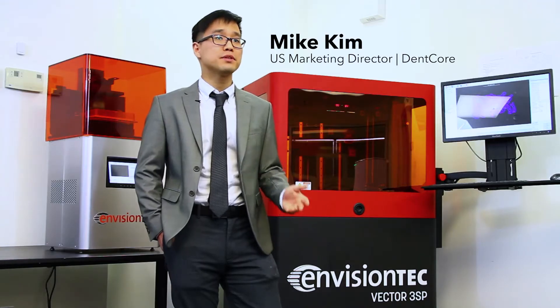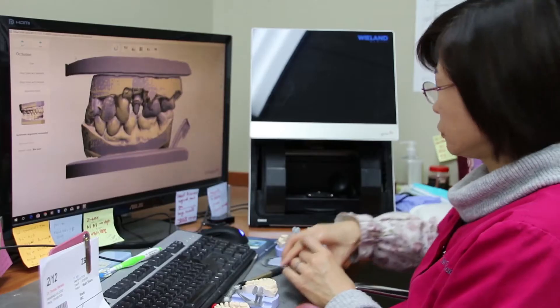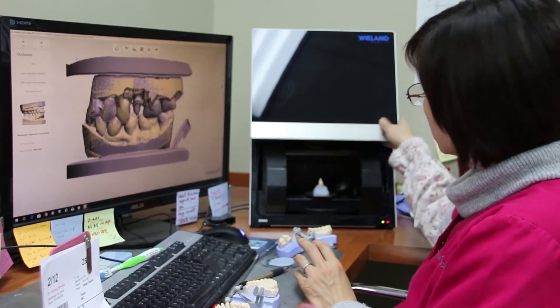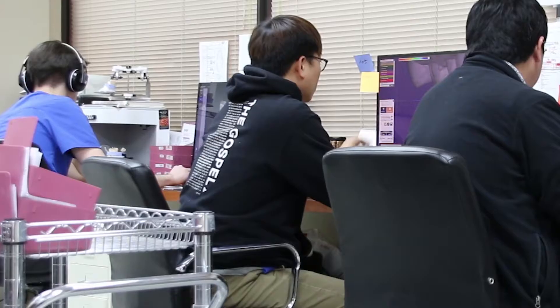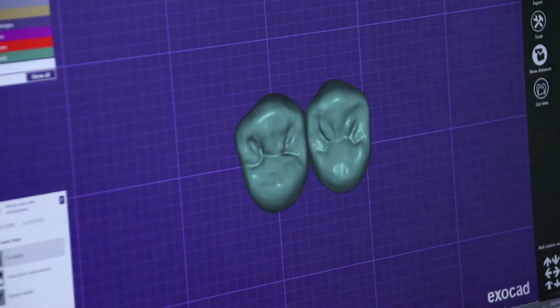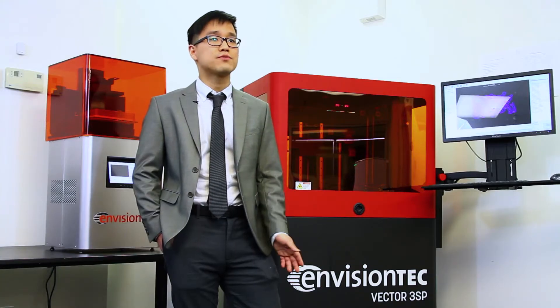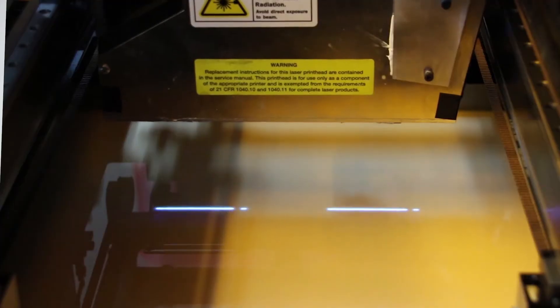For models, they are simply ditched and hollowed so that they can be printed accurately. The dentist either takes a traditional impression of the patient's current teeth or takes an intraoral scan. These impressions are either scanned or imported into the design software where trained technicians take into account the doctor's prescriptions and dental anatomy to design the product. After this is done, the designs are transferred to our manufacturing department where they are loaded onto the machines and printed.